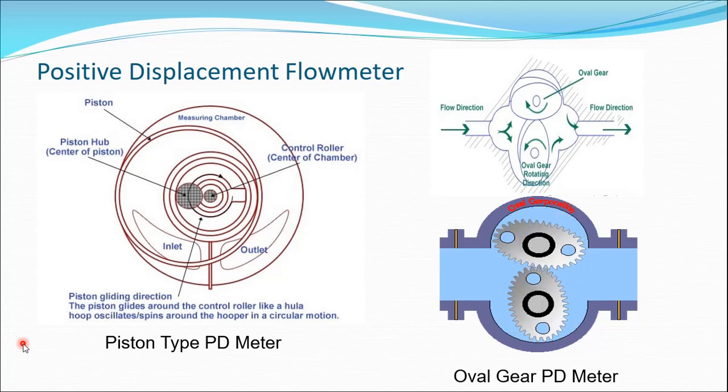These are also known as the oscillating piston flow meters. That is this one. And these are one of the oldest positive displacement flow meter designs. These types of meters are mainly of single or multiple piston types. Other types available are double acting pistons and rotary pistons. The selection of a particular type of piston meter depends on the range of flow rates necessary for an application.